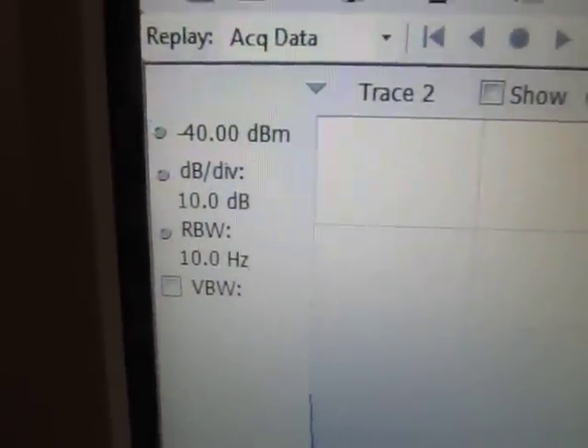To start off with, I've got the analyzer set up here for looking at frequency range from 1 Hz out to 3 kHz, resolution bandwidth of 10 Hz. And I can see that I'm getting a spectrum update here about 3 spectrums or so per second.